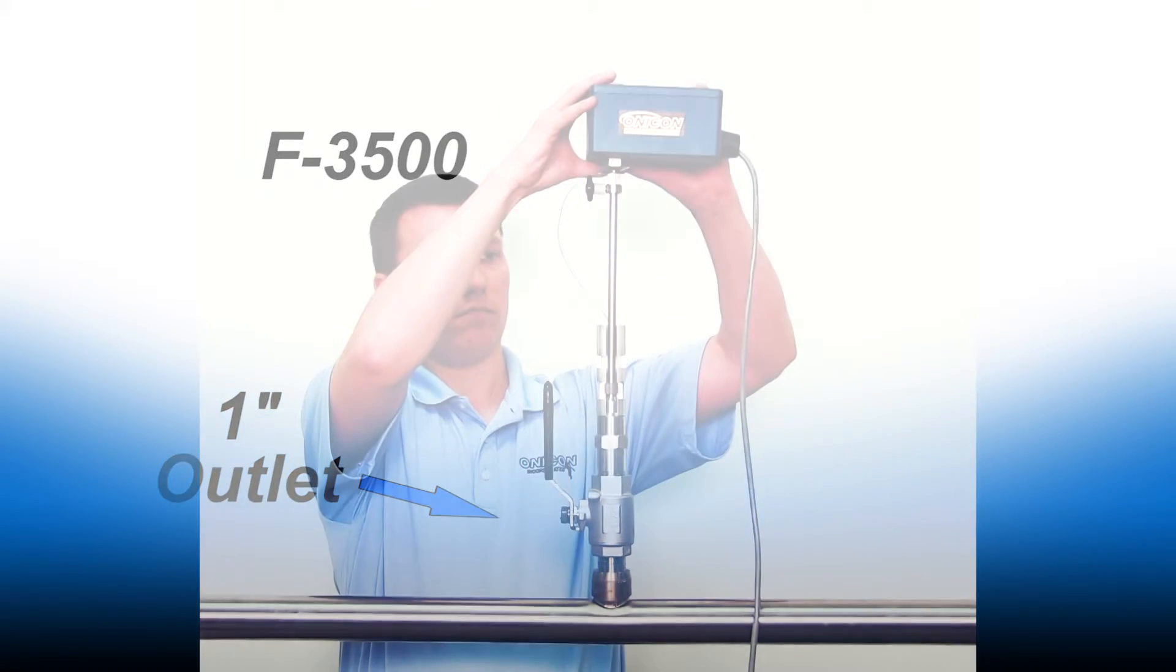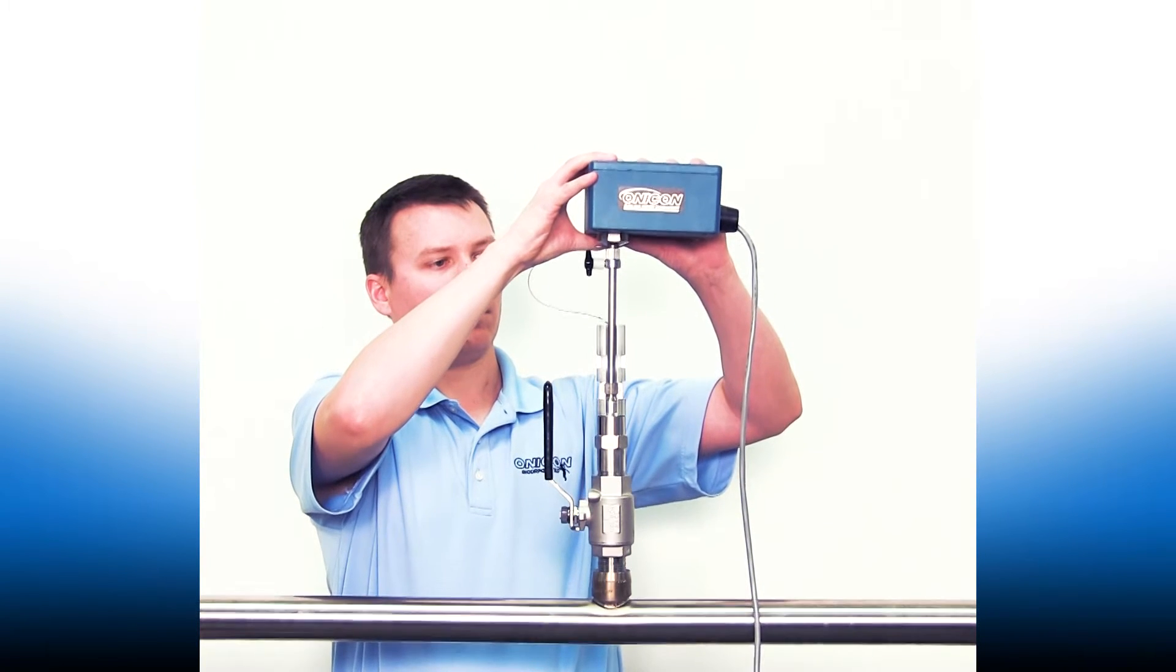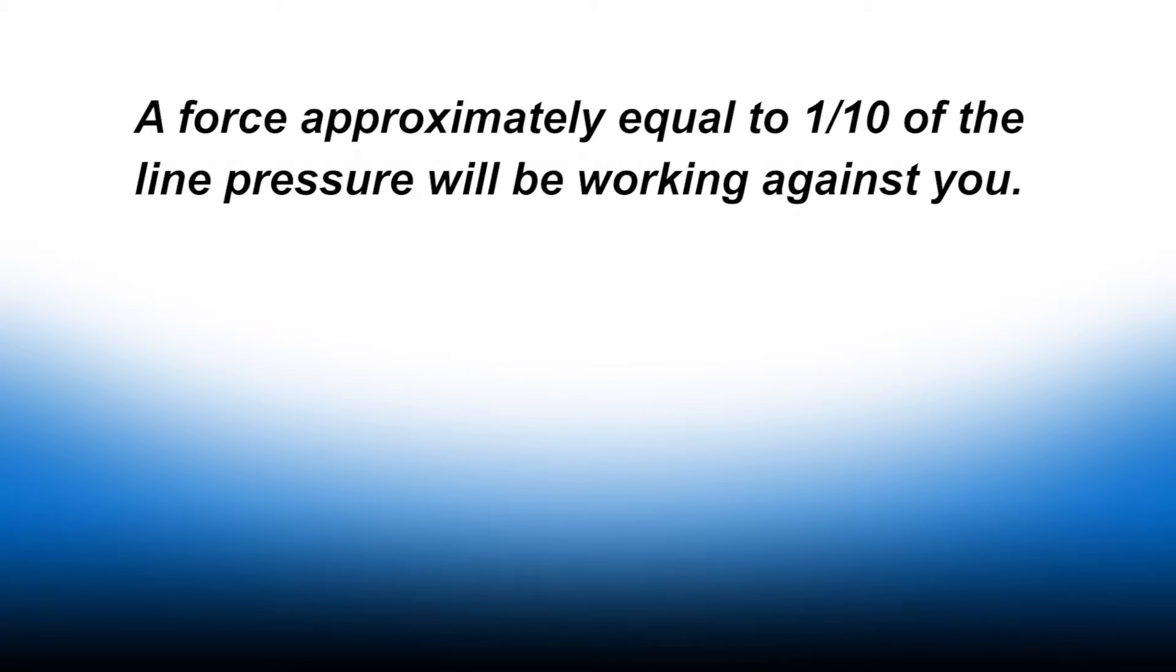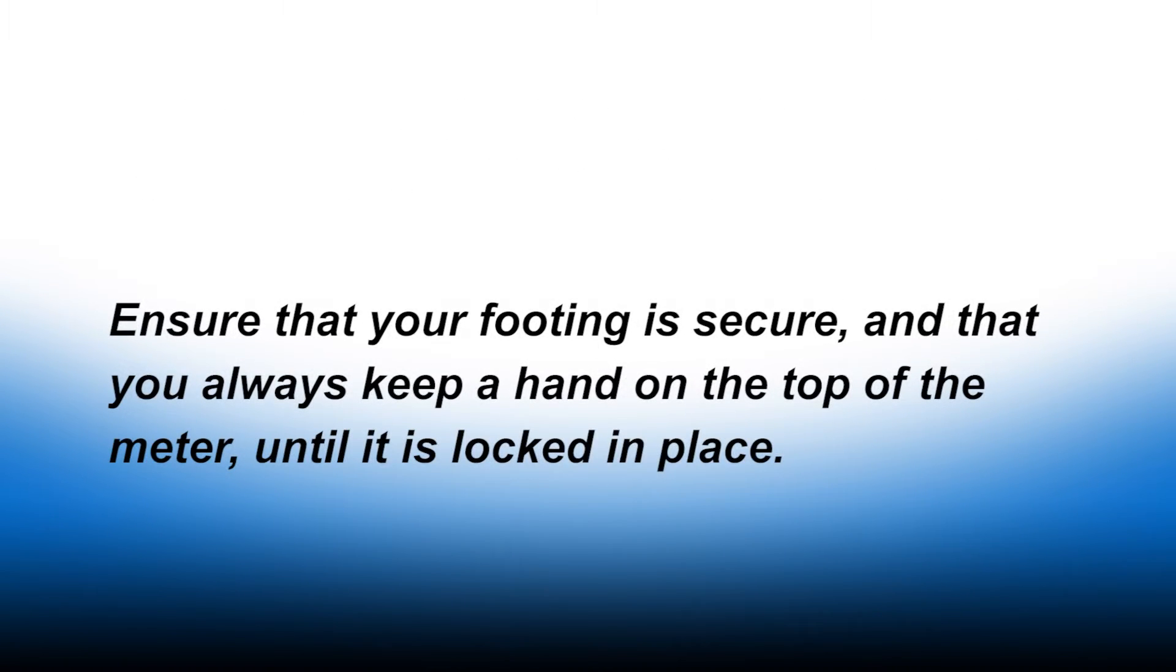While pushing the F3500 into the pipe, a force equal to approximately one-tenth of the line pressure will be working against you. Ensure that your footing is secure and that you always keep a hand on the top of the meter until it is locked into place.